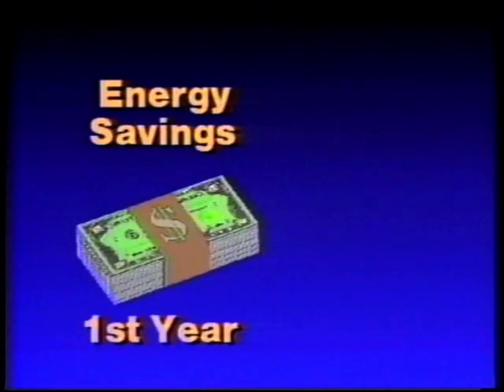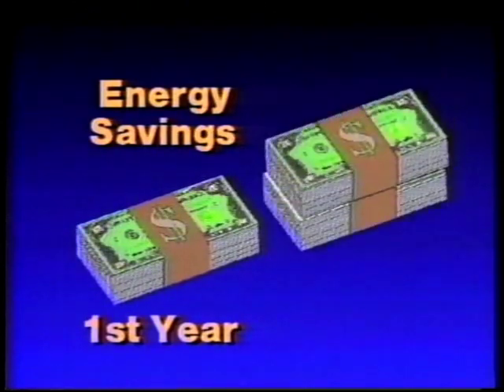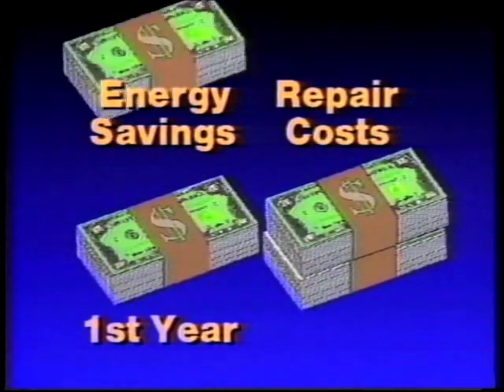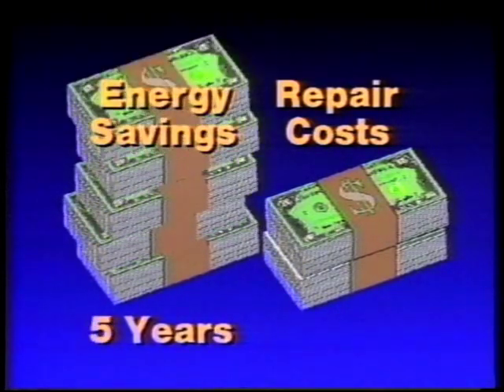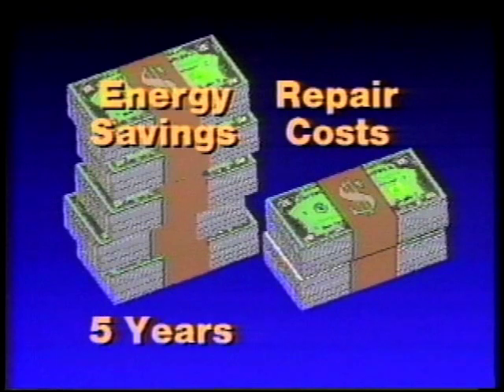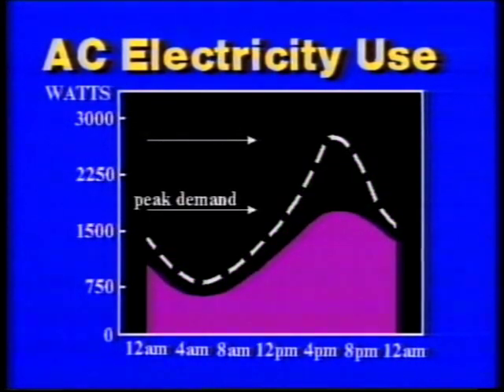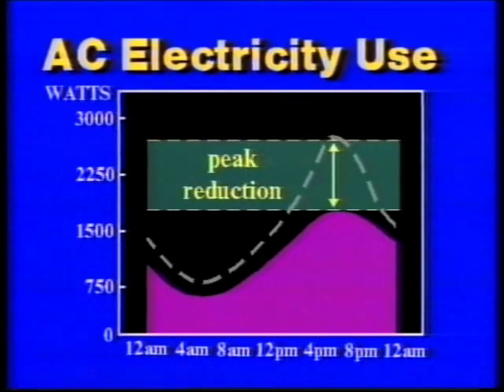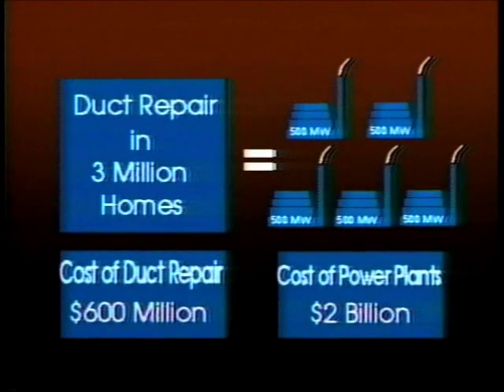Fortunately, duct repair can substantially reduce this energy waste. Based on research in Florida, duct air tightening can save $110 per year. Since the cost of such repair is in the range of $100 to $400, it can pay for itself in about two years. Duct repair can also lower air conditioning electricity use during the utility's peak demand period, reducing the number of power plants needed. It is estimated that duct repair in three million Florida homes, at a cost of about $600 million, could eliminate the need for five large power plants costing about $2 billion.